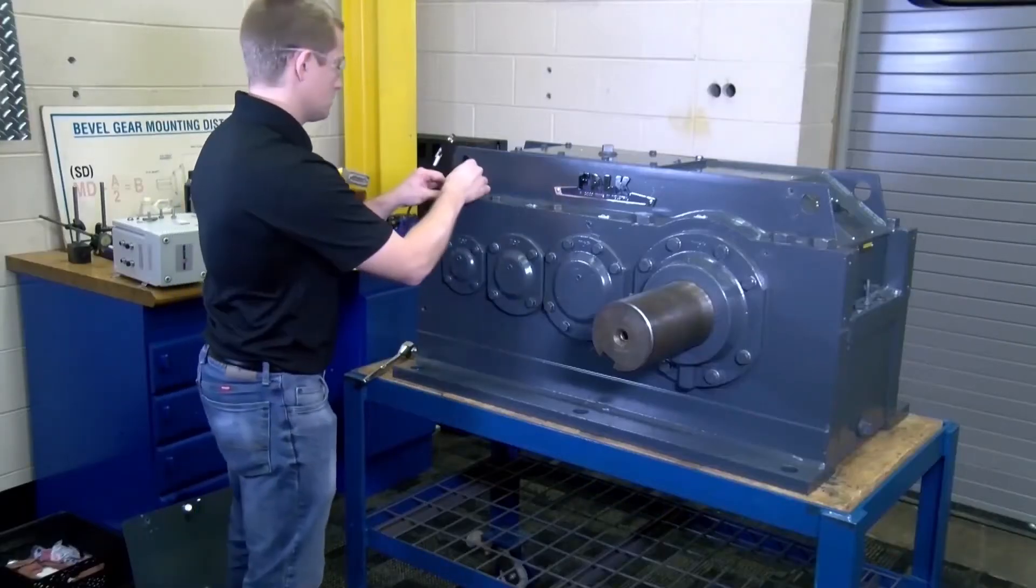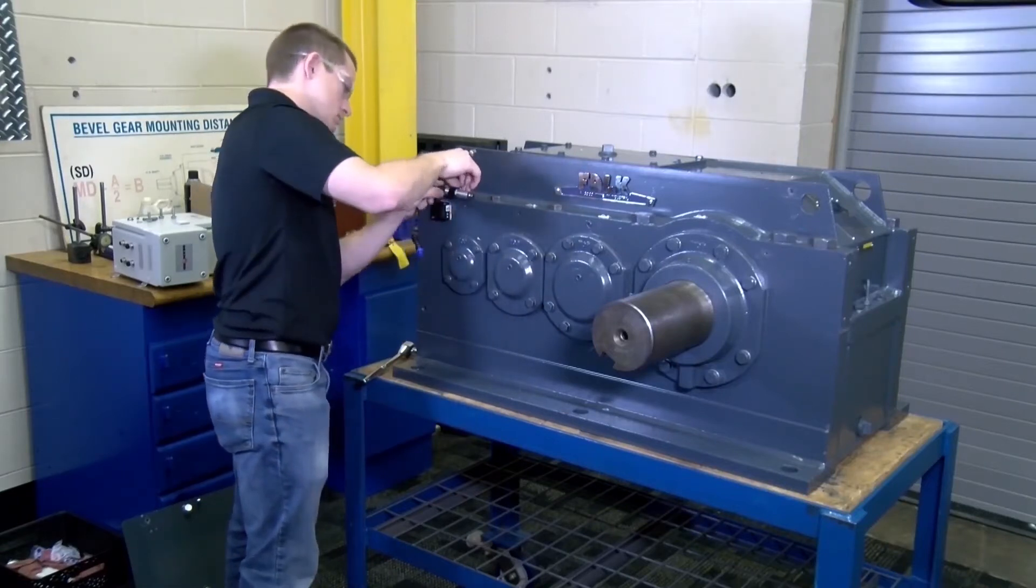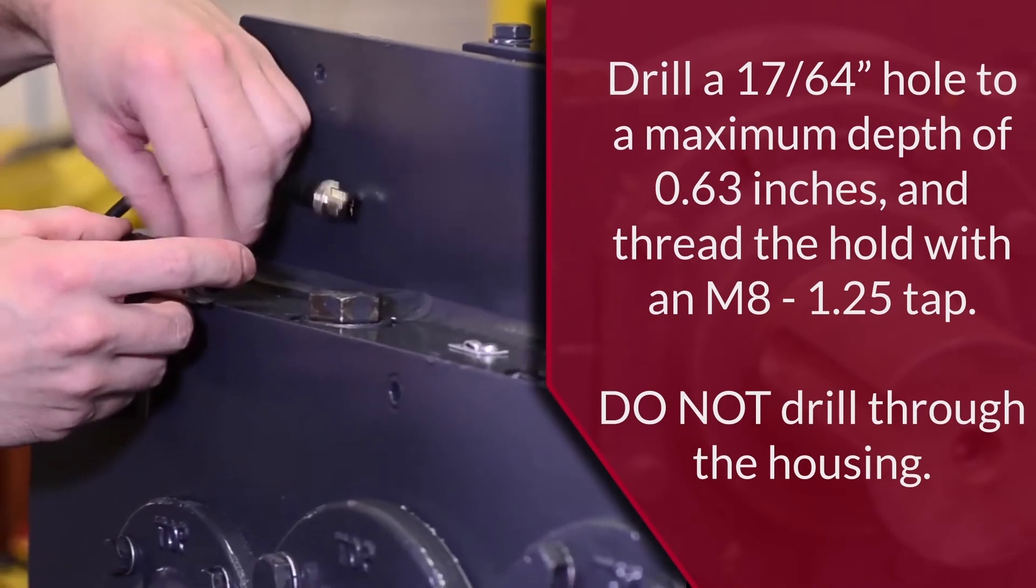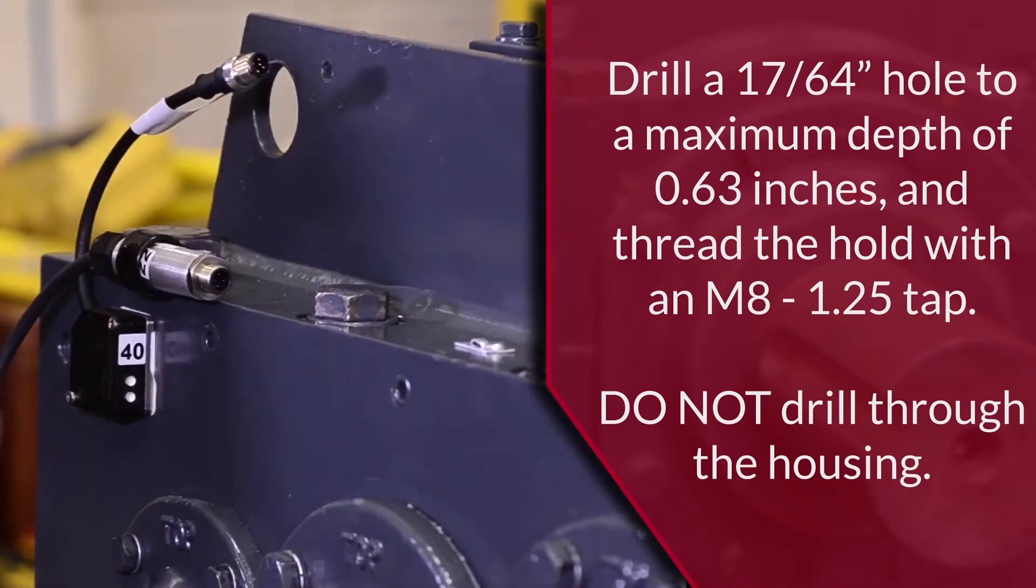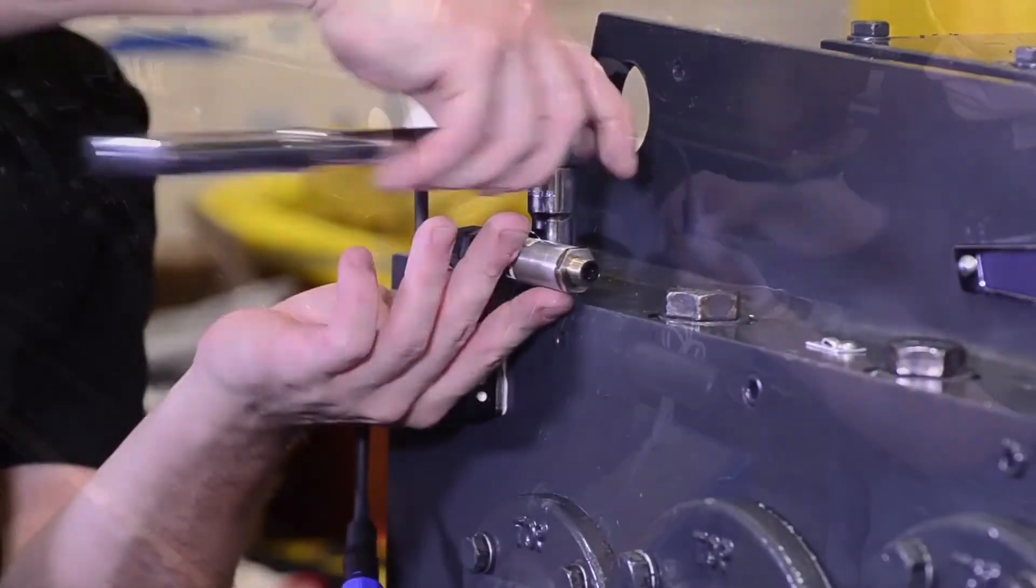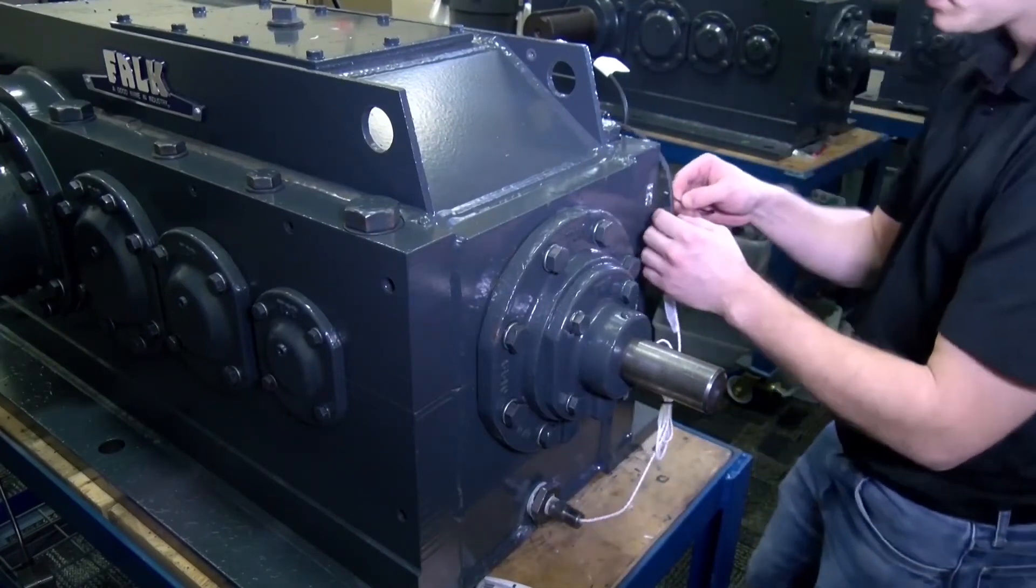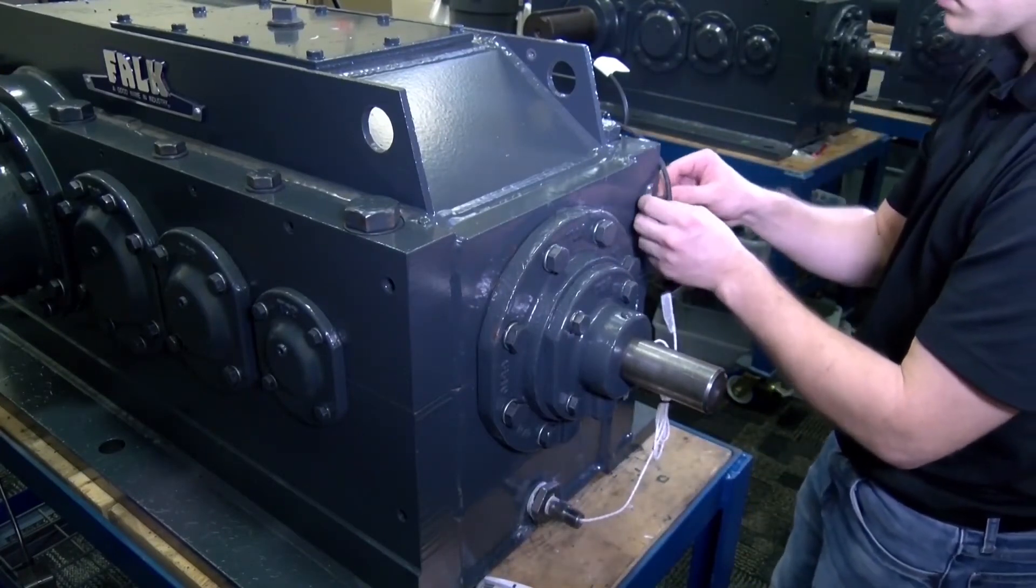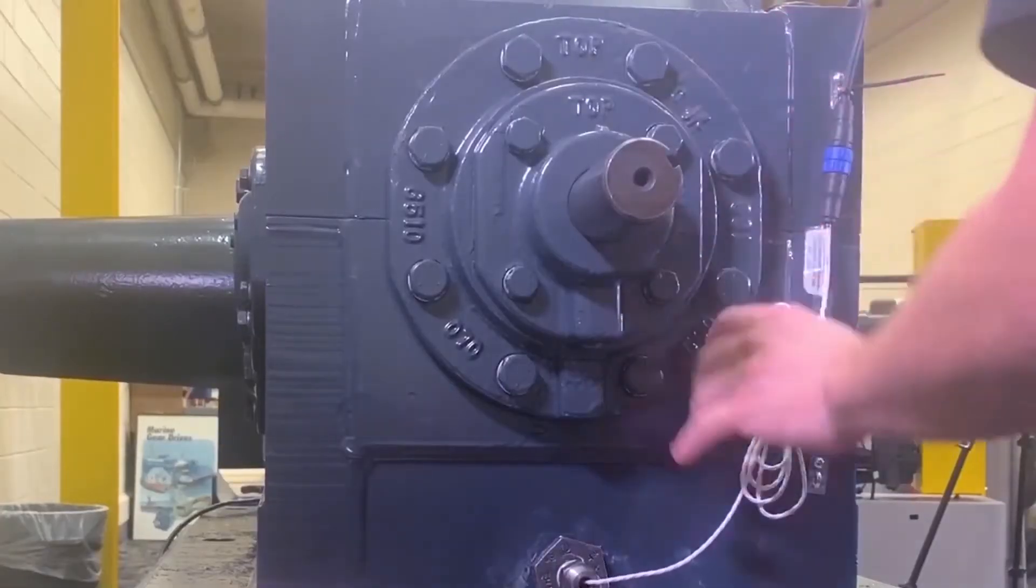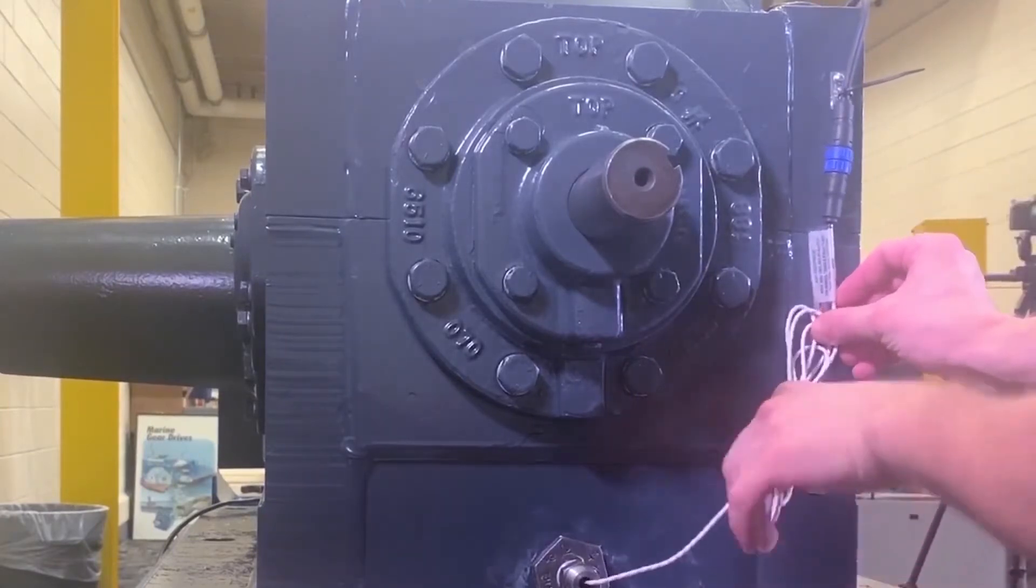Select a suitable location to mount the P-clip to secure the Modbus converter to the housing. Generally, the best location will be on the end of the drive near the bottom, or on top of the ledge where the split bolts are located. Attach the Modbus converter to the temperature sensor by connecting the blue end of the sensor cable with the blue end of the converter. Install the converter into the P-clip and attach to the drive with the M8 hardware.